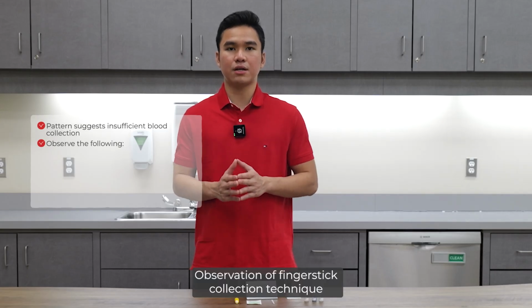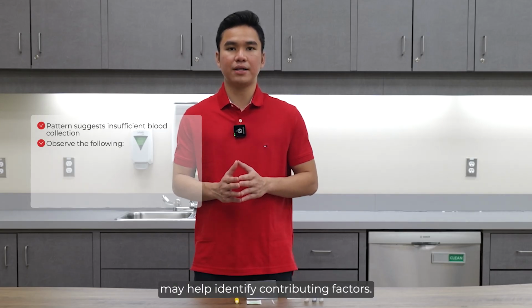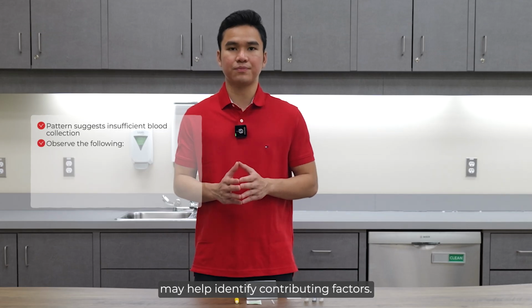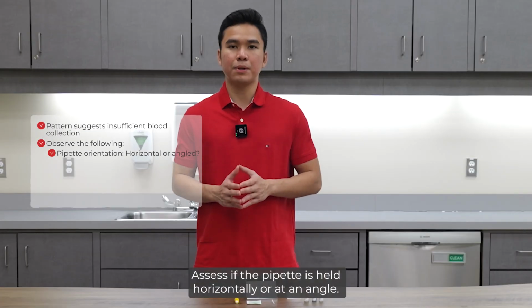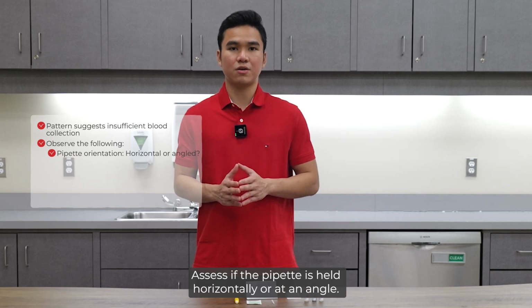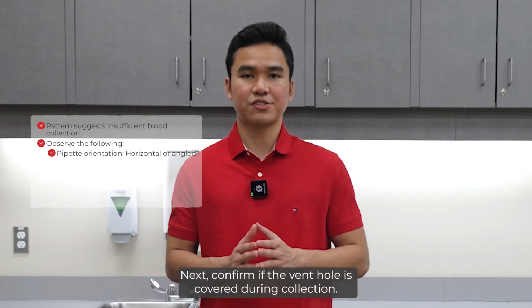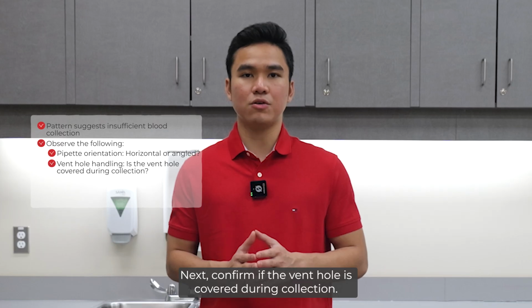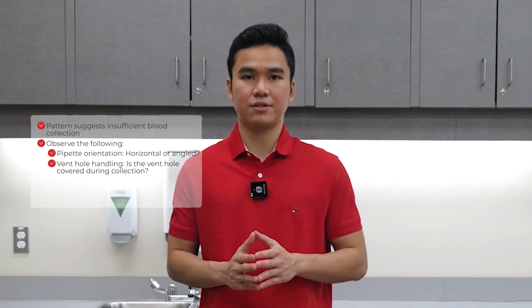Observation of fingerstick collection technique may help identify contributing factors. This includes pipette orientation. Assess if the pipette is held horizontally or at an angle. Next, confirm if the vent hole is covered during collection.